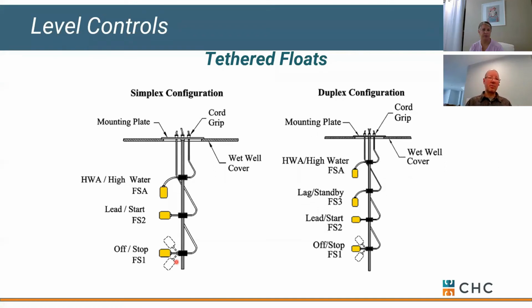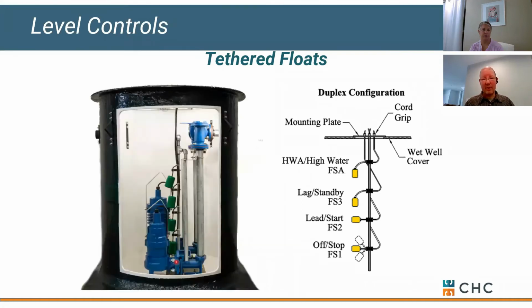Now let's talk about floats real quick, or how we control pump operation. Simplex is very simple. Most of our applications are duplex, which means as water is rising in our basin, these floats will raise or drop. So let's talk about that real quick in case you're commissioning or dealing with the startup. As water comes up and raises the first float, nothing happens. And you might be really disappointed, but bear with me, okay? As water comes up and raises the second float, now we turn on what we call our lead pump. And if that pump's doing its job, the water level drops, and it doesn't shut off until the first float drops. Float switch 2 is going to drop, but the pump continues to run until float switch 1 drops.